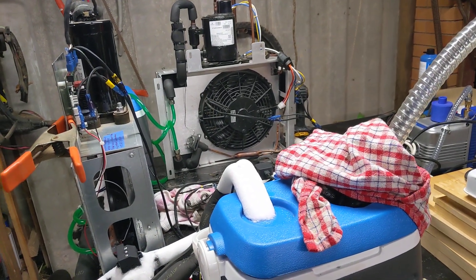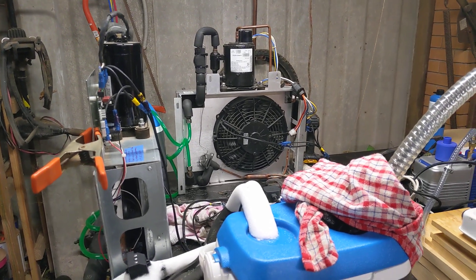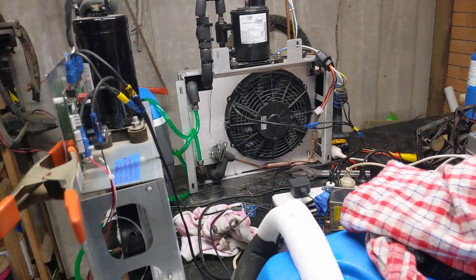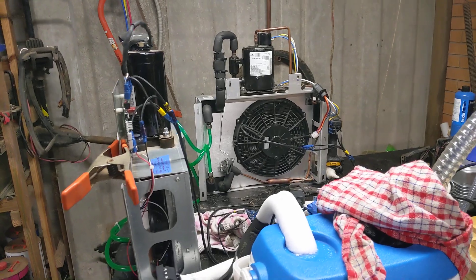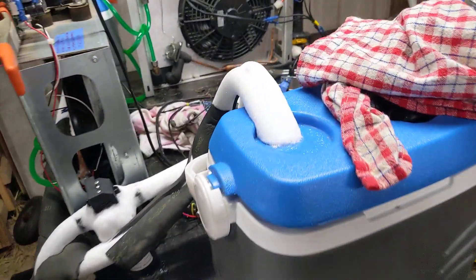As far as I can tell, the glycol stopped flowing, so I have to assume it's because the heat exchanger got clogged — maybe because it froze, maybe because of detritus. But I shut it down and flushed it backwards and it started up again. I turned it off for a test and this maintained negative 40 by itself.